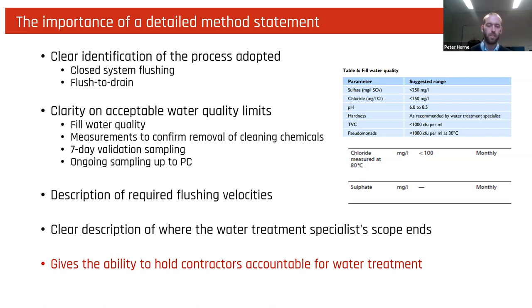We want clarity on all acceptable limits, whether that be through fill water quality, measurements to confirm removal of cleaning chemicals, your 7-day validation sample with particular interest to inhibitor levels. So we want minimum and maximum inhibitor levels throughout. That's to make sure that overdosing doesn't become a problem. We're very aware that underdosing is a problem, but overdosing also can have significant risk on your system. Just on the right-hand side, you've got two outtakes, one from BG29 and one from CP1 2020.